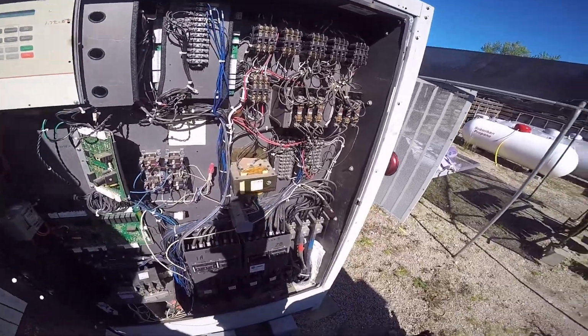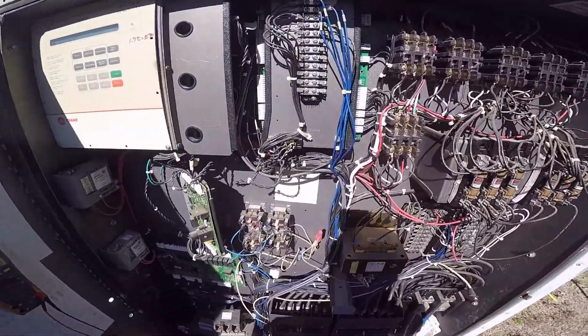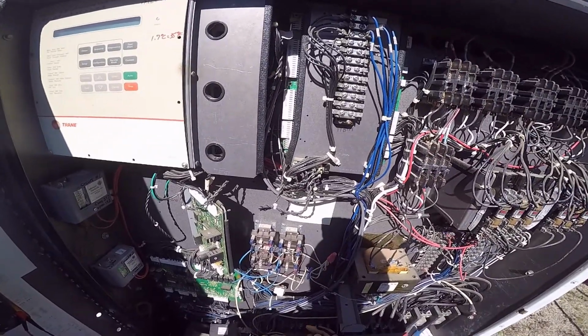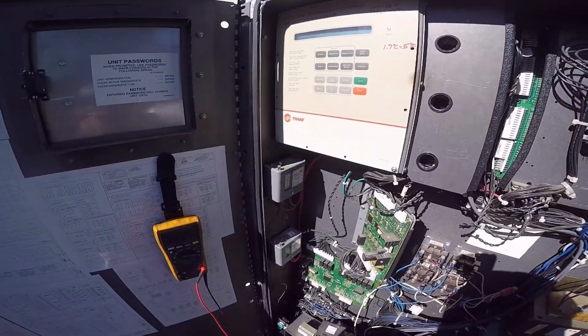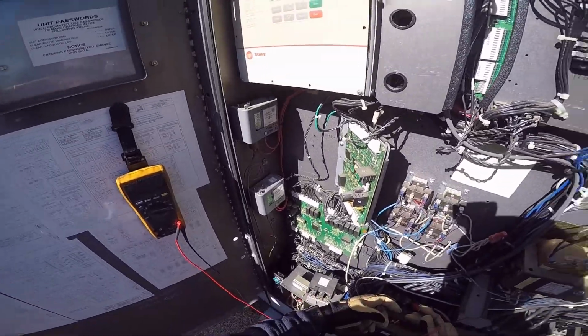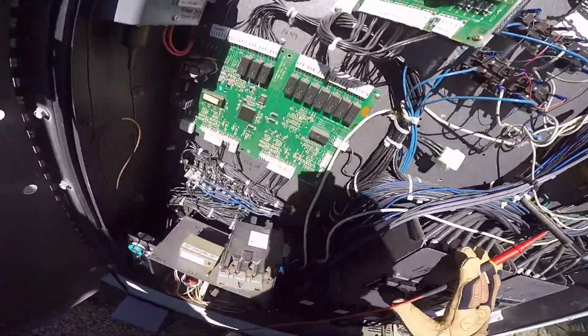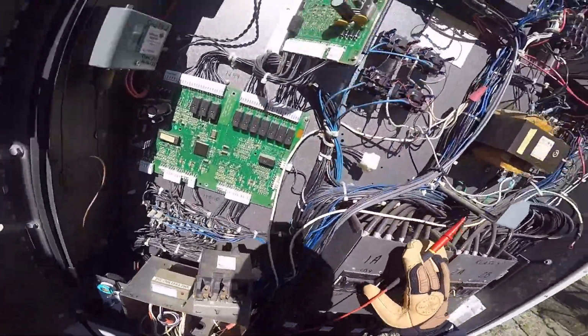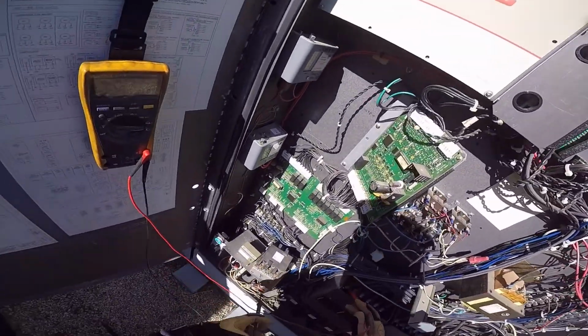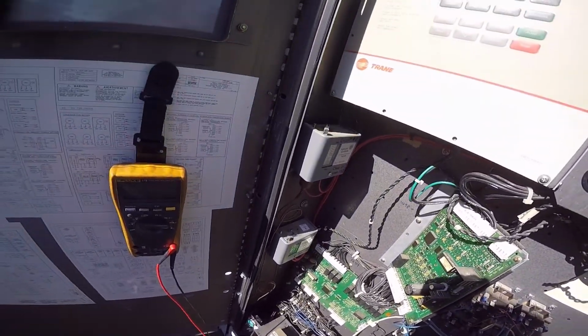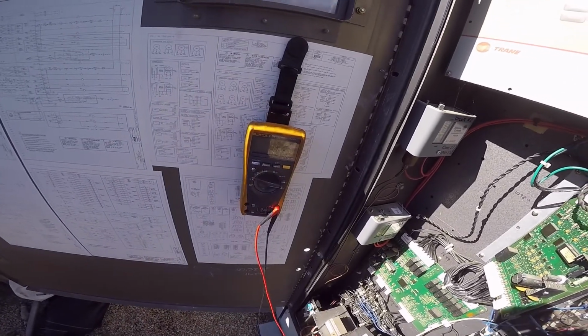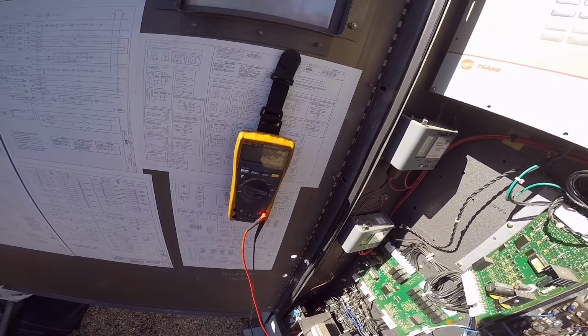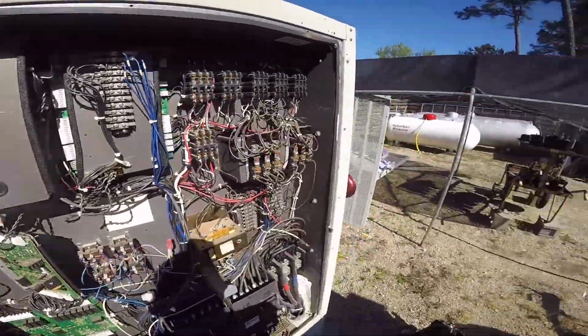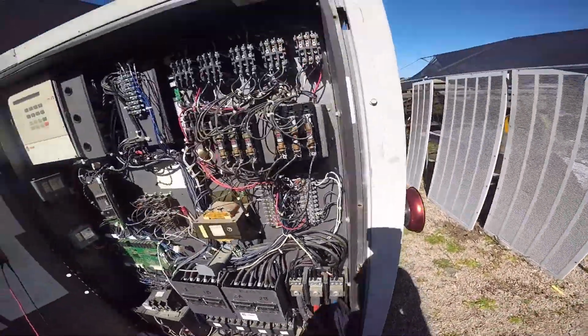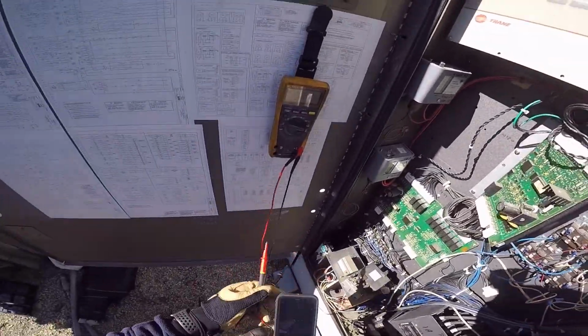Now, if you follow the wires to the top of the circuit breaker, you have the same legs over here - L1, L2, right there, 211. Down here on the bottom, what we're going to do is check the drop through the circuit breaker. I'm looking for 0, and that's 3 millivolts, which is technically 0.